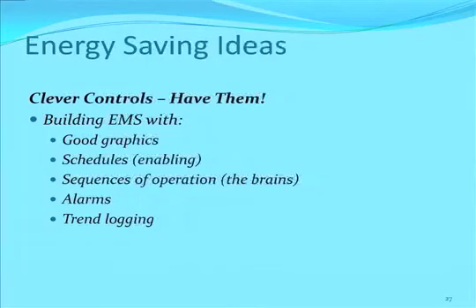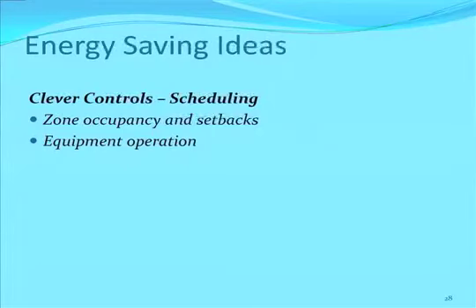It needs to have alarms and also trend logging, so that you can identify why is it that now I'm using more power than I did yesterday when the temperature was the same outside and the occupancy was the same. Scheduling, make sure that you have your setbacks clear with your current occupancy and your equipment operation.